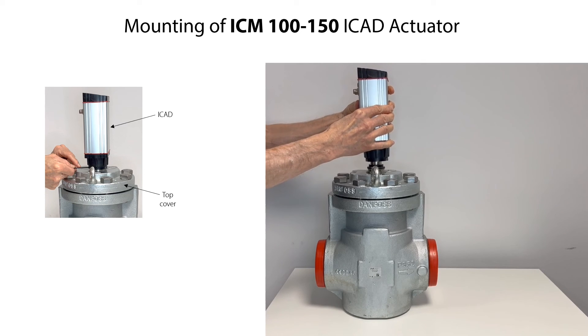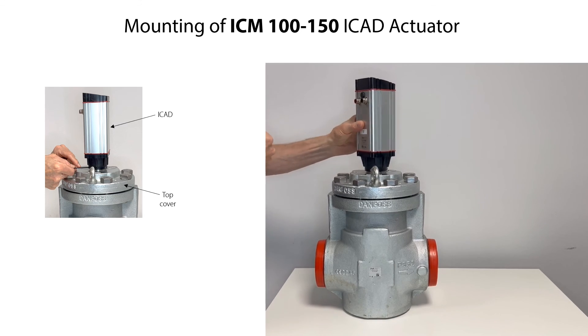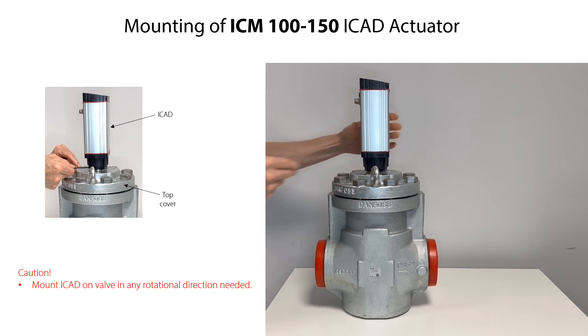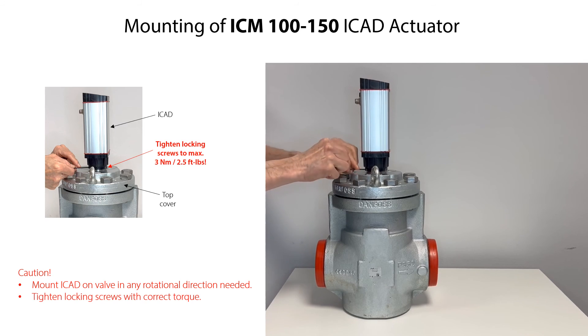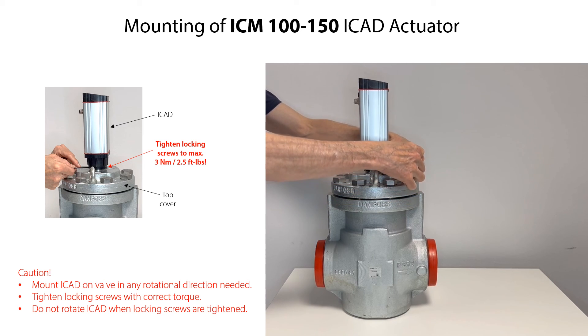Carefully mount the ICAD actuator onto the valve top and press it downwards until there is full contact with the top cover. You can position the ICAD in any rotational direction as needed. Then tighten the locking screws on the ICAD actuator with the specified torque. Do not move or rotate the ICAD once the locking screws are tightened.